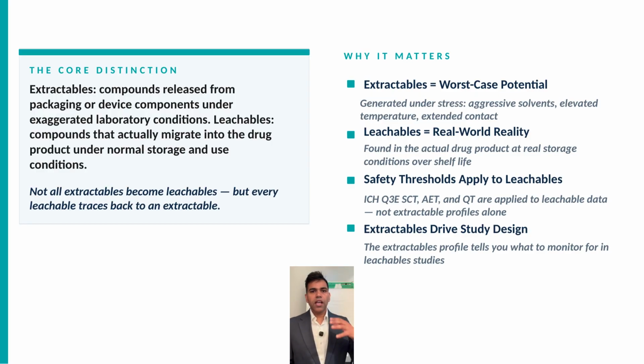Leachables are what actually migrates into your drug product under normal, real-world conditions of storage and use. Every leachable traces back to an extractable, but not every extractable becomes a leachable. That distinction drives your entire testing strategy. The extractables profile tells you what to look for, and the leachables study confirms what's actually there.